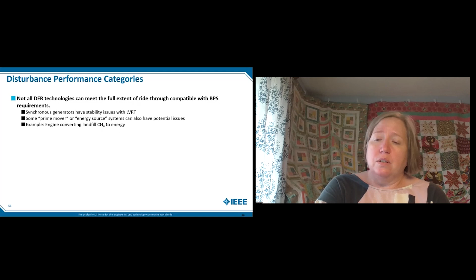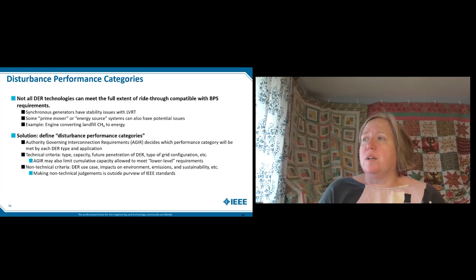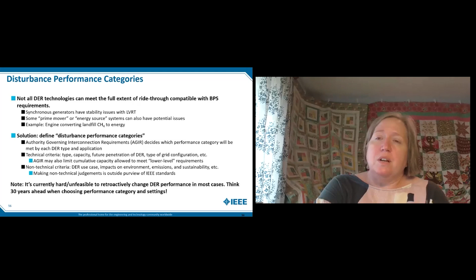The authority governing interconnection requirements decides on the performance category met by each DER type and application. The technical criteria look at the type, the capacity, the future penetration, and the type of grid configuration. The AGIR may limit the cumulative capability allowed to meet lower level requirements. Non-technical stuff is not the purview of IEEE standards. And if you're wondering, I will get into what we did. It's really important to future-proof this a little bit. You may want to make sure your inverters can all meet the higher category versus the lower category, because you're not going to be able to really change that in the future.